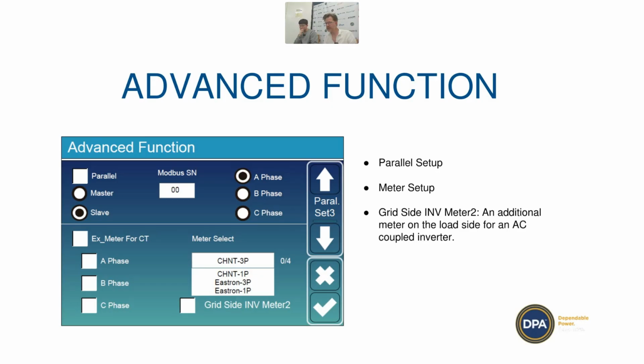If you're using an external meter, you're going to set that up here as well. So if you're using the CT that comes with it, then you don't need to do anything here. If you are using an external meter, you need to put on external meter for CT, and then you need to select Eastron 1P if you're using the Eastron SDM 120, which we sell.